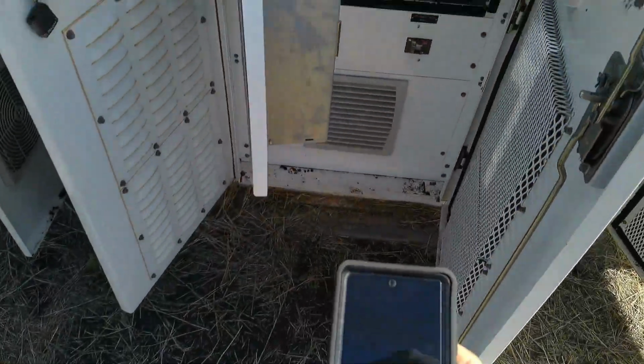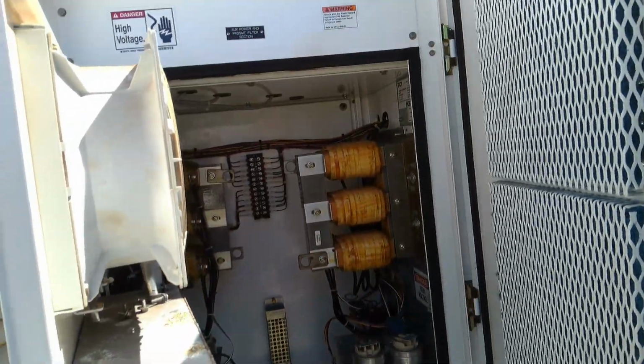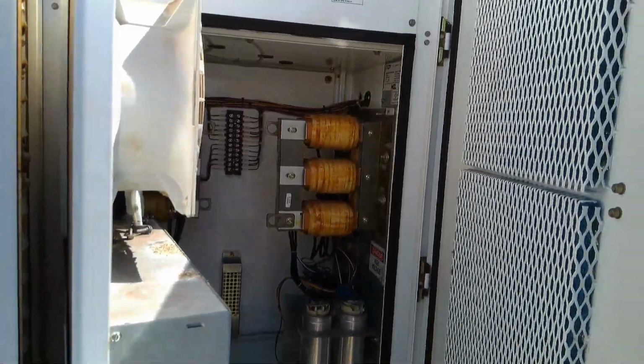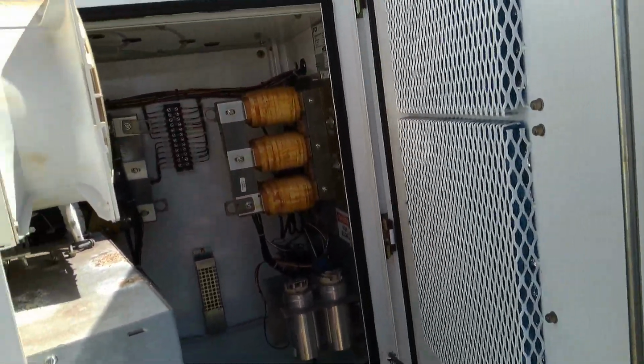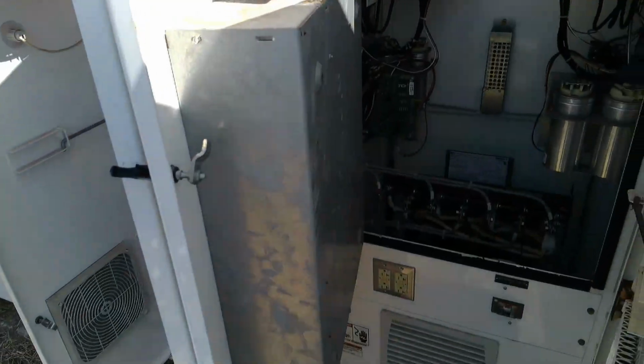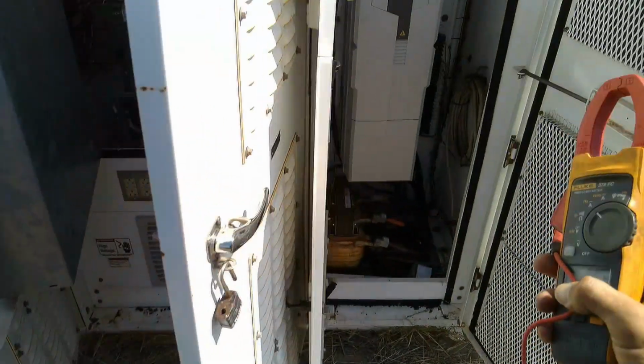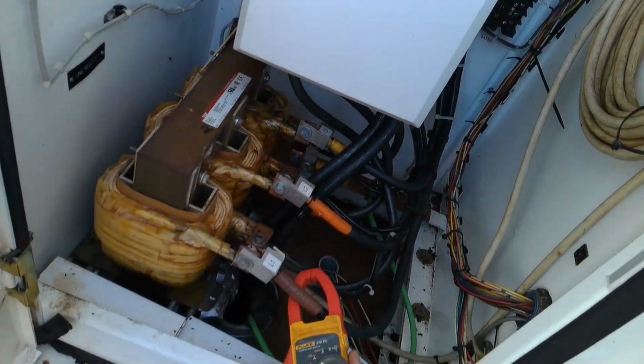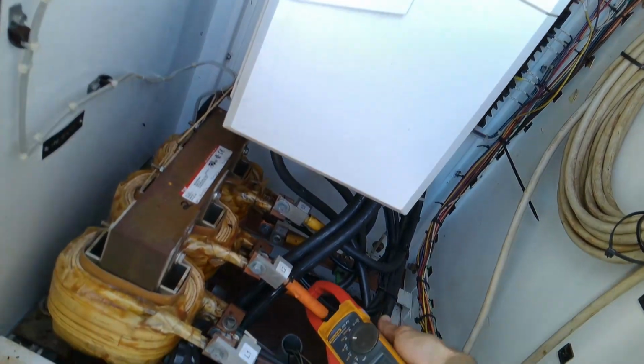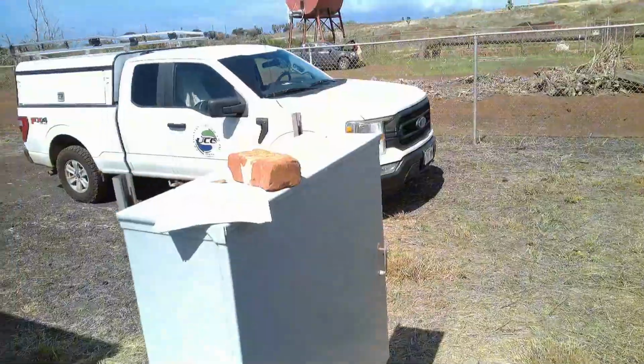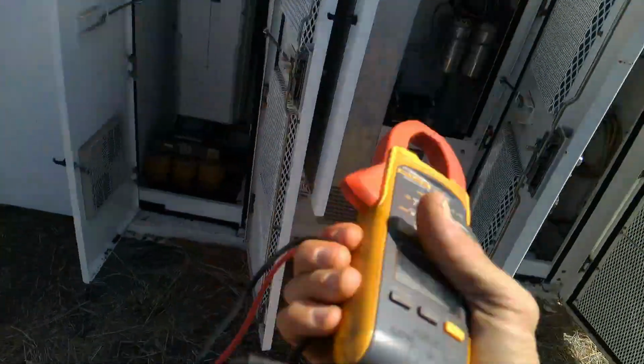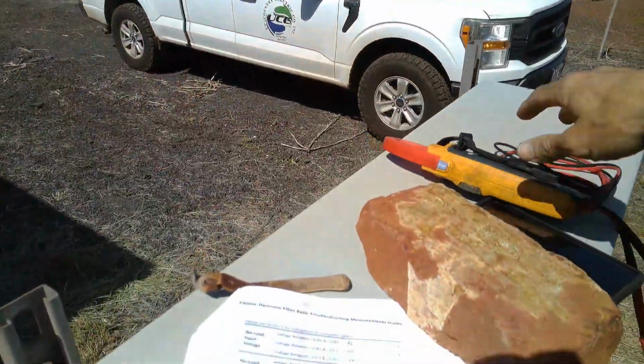So now we're going to connect to this bad boy with Bluetooth and engage the contactor. Alright, I got the factory password to force close that contactor. It's sucked in, and then... oh, there it goes. 32, 32. There we go. Just took a second. And now it's open. 32 amps. Alright, that's what we were after.